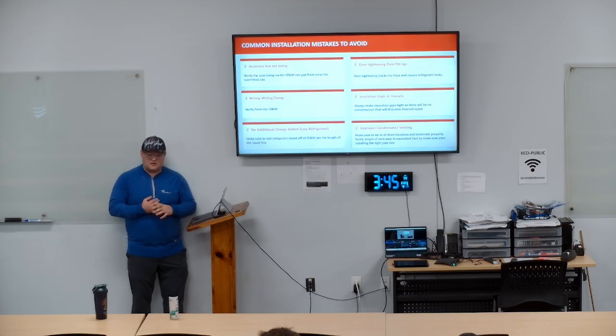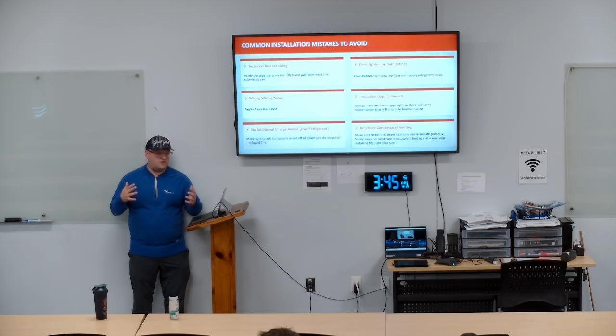Make sure that we're adding the additional charge. Already talked about that. And then improper condensate and venting on things. If we end up venting an indoor furnace, read the book, read the IOM. You're not allowed to go so far with certain sizes. Just because the taps off the top for an intake and an exhaust are 2-inch doesn't mean you could run it in 2-inch all the way. There's literally a book that'll say if it's over 20 foot, you got to up it to 3-inch.